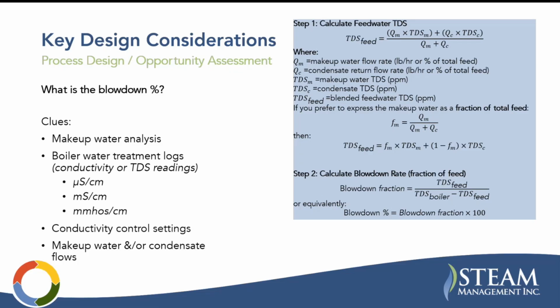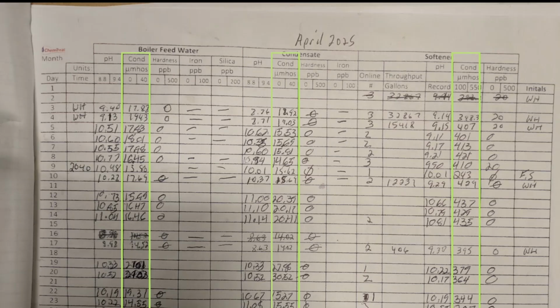Sometimes you just have a rough idea of condensate return and maybe a makeup water analysis from the water utility, and you can get to a reasonable TDS level in your feed water. In the end, once you have that, you can use that and what the boiler recommended limit is, or you can use what they're controlling to, which you can find on the controller screen, and you can calculate the blowdown percentage. So that's your waste heat stream that's going to drive the energy savings for the whole deal.